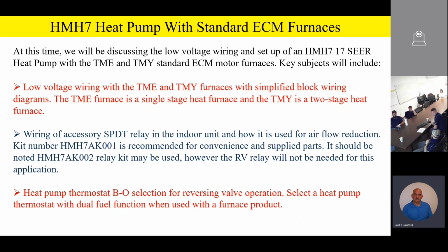Now, please remember also, team, that the heat pump thermostat still has to have that BO selection for reversing valve operation, and make absolutely certain that you select a heat pump thermostat with dual fuel function. Let me say that again. You have to have a heat pump thermostat with dual fuel function anytime you use it with a furnace product.